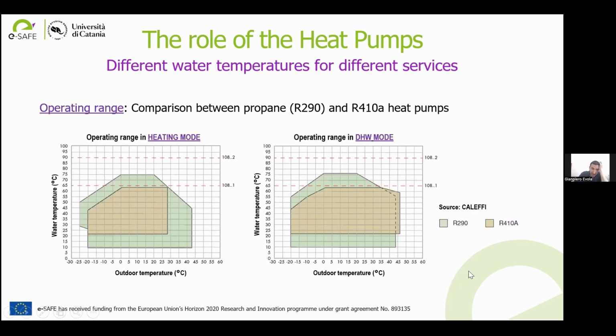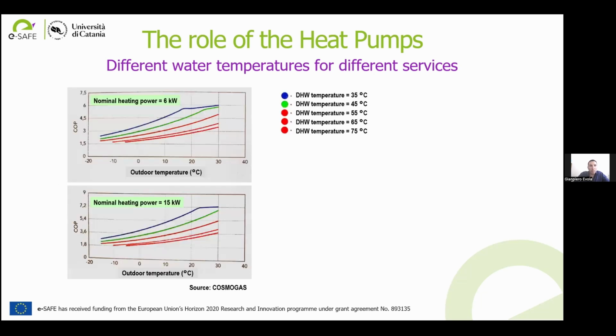These two plots compare the operating ranges of a commercial unit with propane, the green areas, and with a traditional refrigerant, the brown area. You can see that the green areas are larger than the brown ones, so we can reach even 75 degrees Celsius on the hot side, on the domestic hot water side. But as I told you, COPs will be lower.